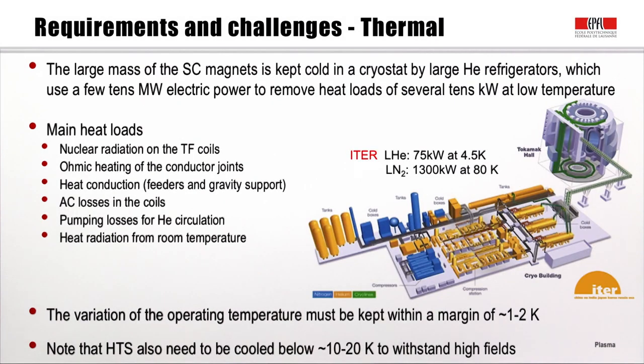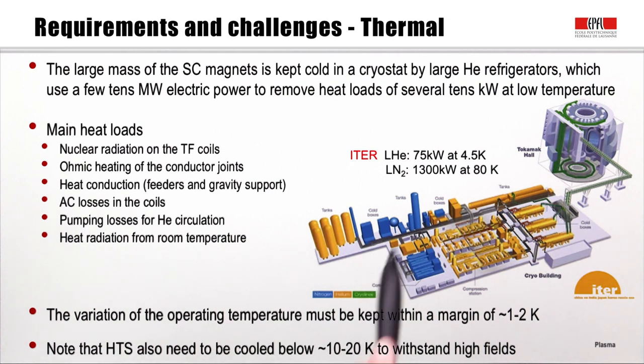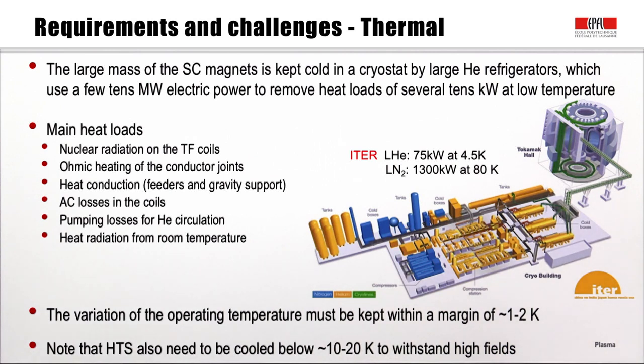In terms of thermal requirements, the large mass of superconducting magnets must be kept very cold in a cryostat that uses very large helium refrigerators — typically a few tens of megawatts of electrical power to remove heat loads of several tens of kilowatts at low temperature. The ITER cryo system has a cooling power of 75 kilowatts at 4.5 Kelvin for the helium circuit and 1.3 megawatts at 80 Kelvin for the liquid nitrogen circuit.